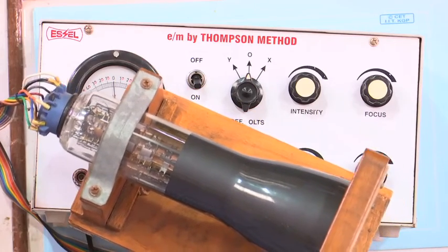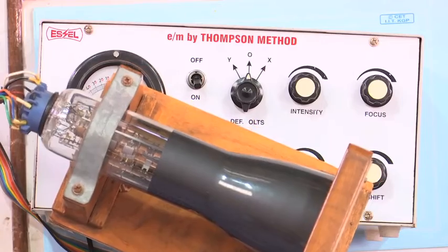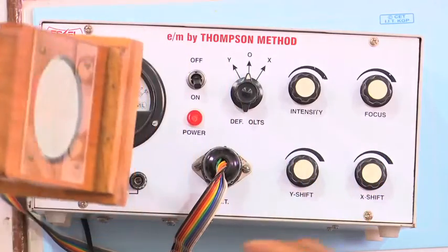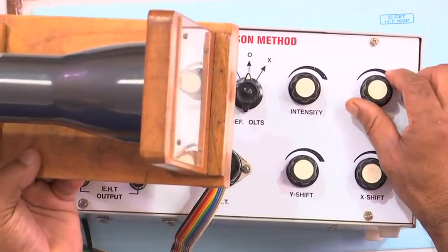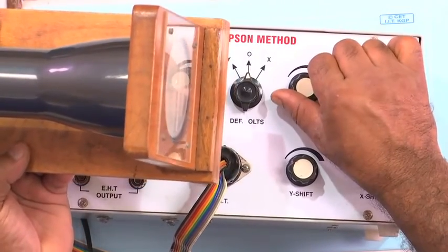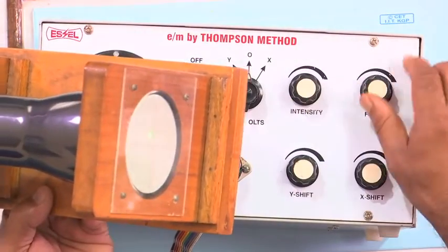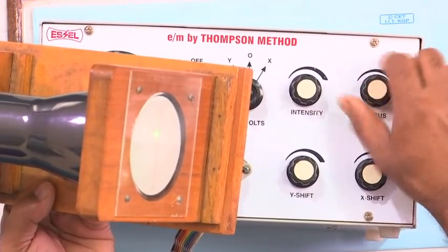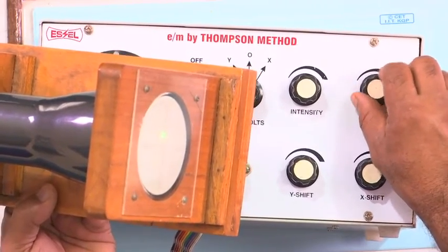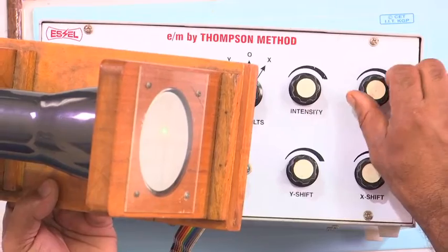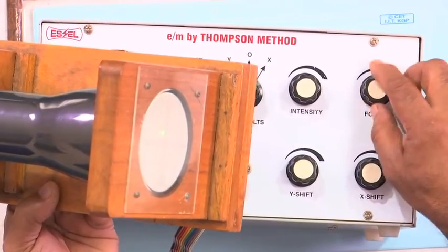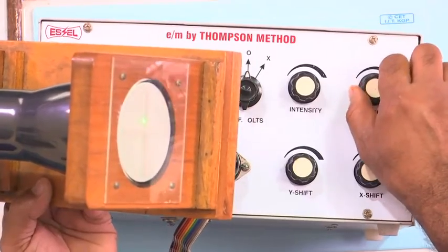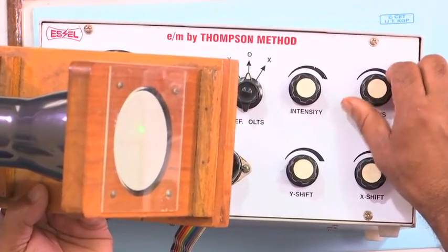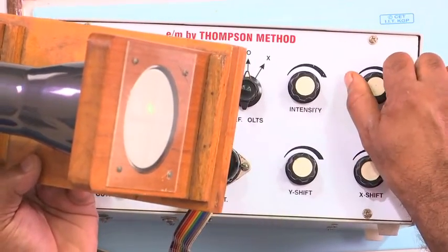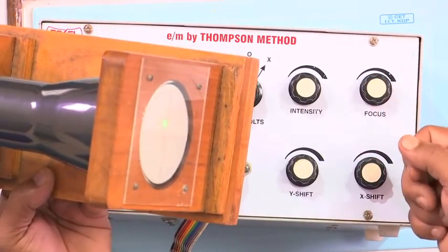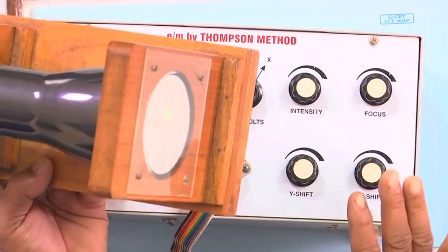So, they will pass through this hole, okay. That way I am converging, focusing the electron. So, here, for this focusing part, I think I have to increase the intensity. Now, focusing means you are making it sharper, it will be a very nice point, okay. So, that is basically the focusing control, the focusing of the electron beam. When I am rotating this knob, what am I doing? I am just changing the voltage of this cylindrical capacitor, okay, nothing else.